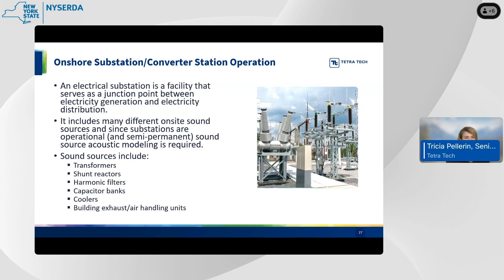Transformers are really the main sound source when looking at a substation or converter station. There are three main sources of sound associated with a transformer: core noise, load noise, and noise generated by cooling equipment or fans. A three-phase transformer typically has sound levels associated with no fan cooling, plus two different levels of sound generated by cooling with fans. The core vibrational noise is really the principal noise source, but it doesn't vary with electrical load.